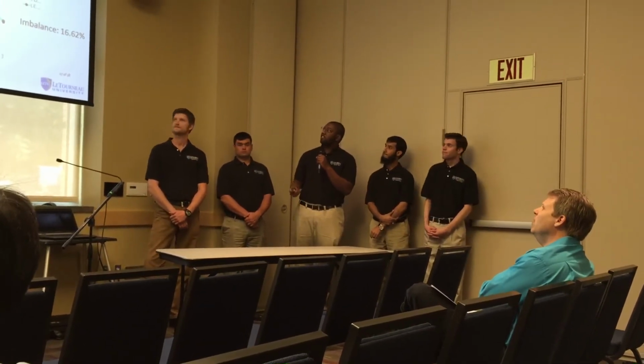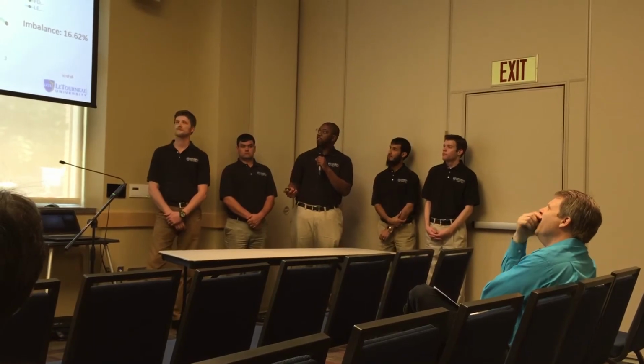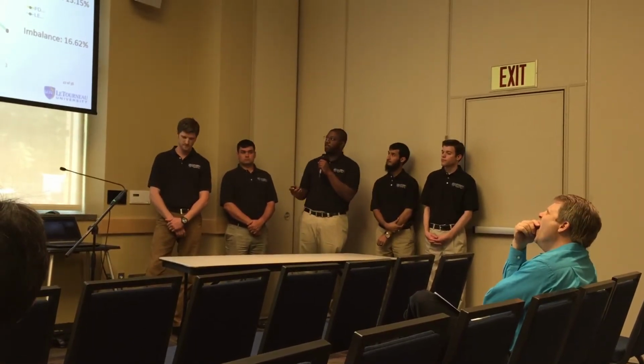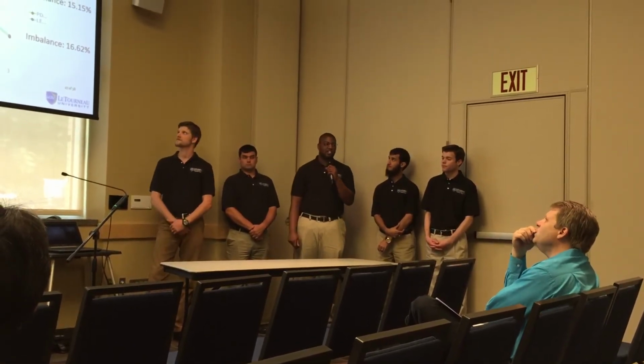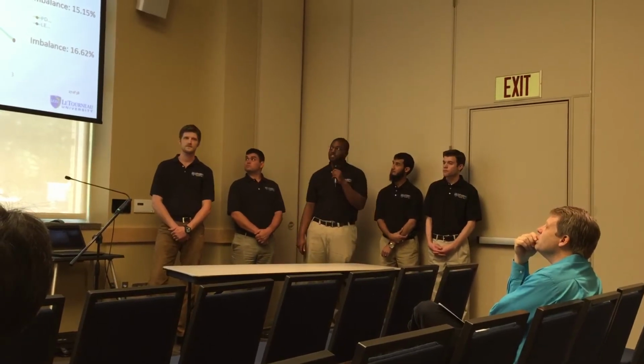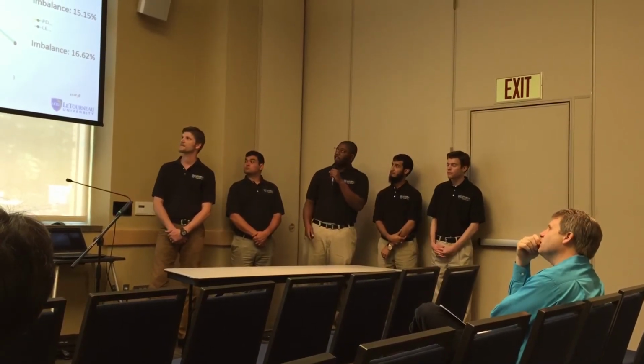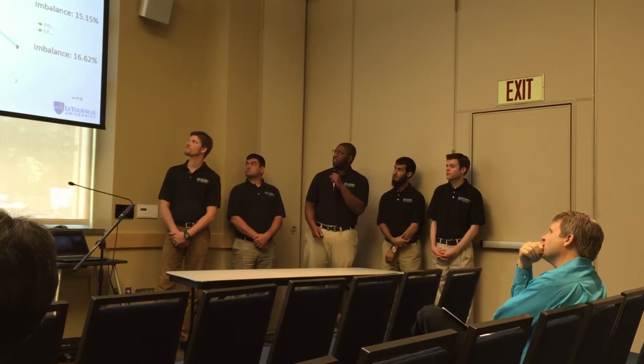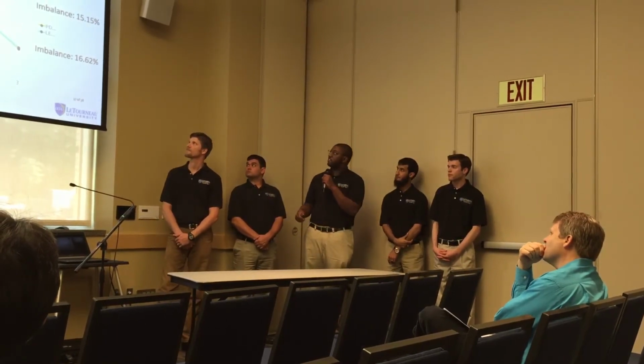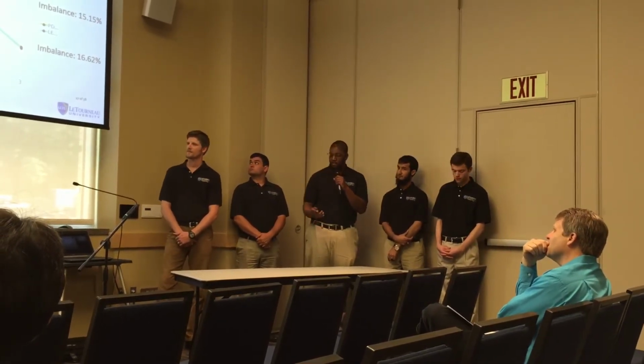This is the resistance imbalance of a bad motor, and you can tell it's a bad motor by how much variation in resistance there is between the 3 phases. As you can see, the PDMA says it's 16.6% imbalance, and our unit says 15% imbalance.